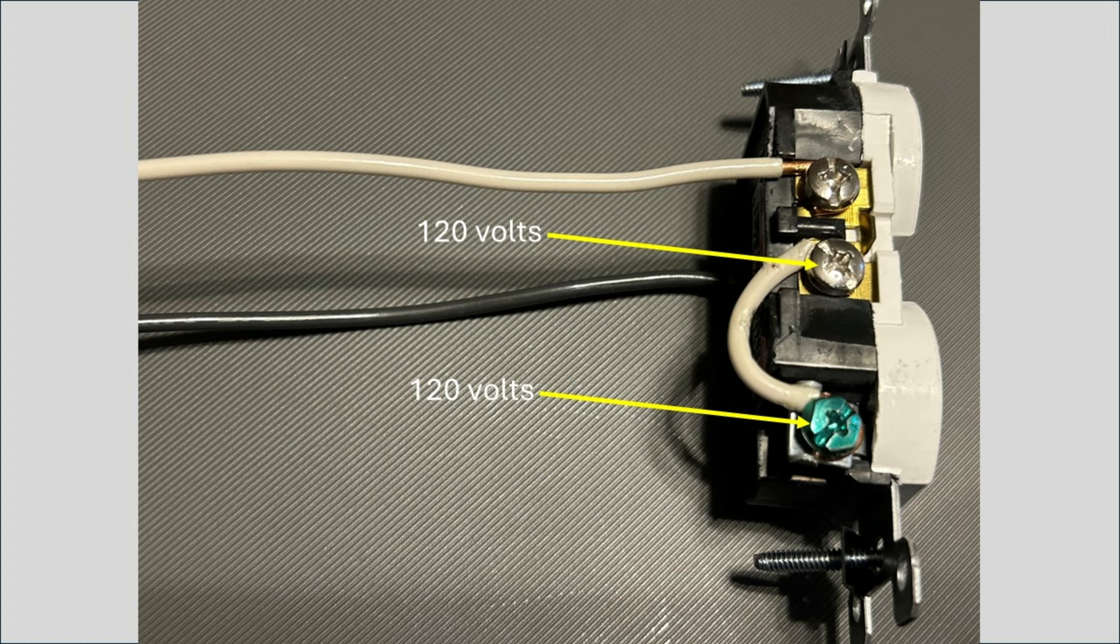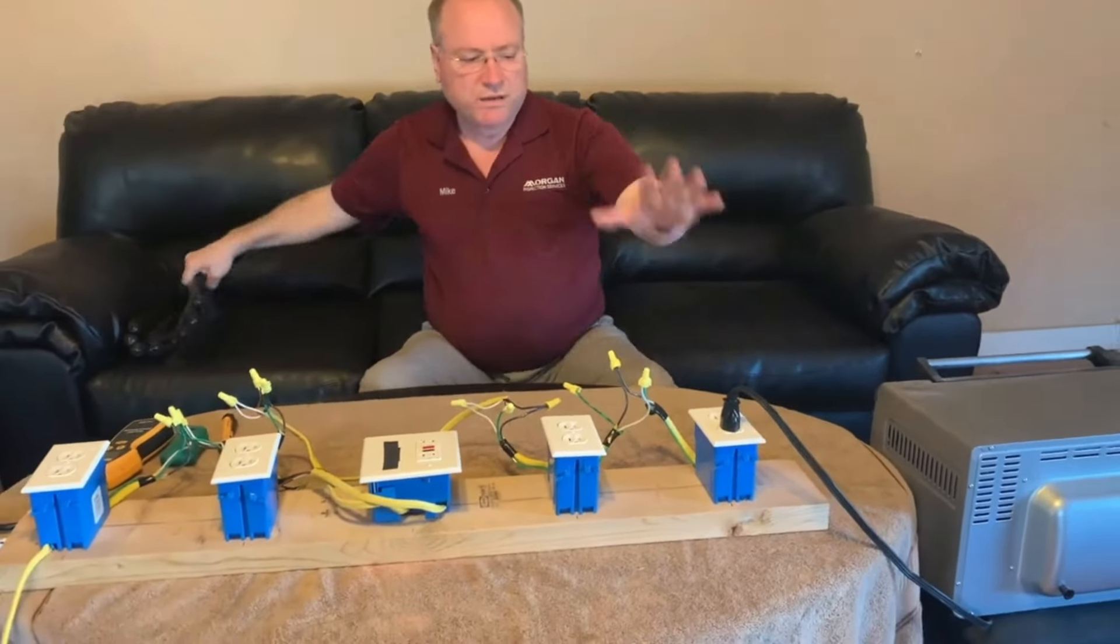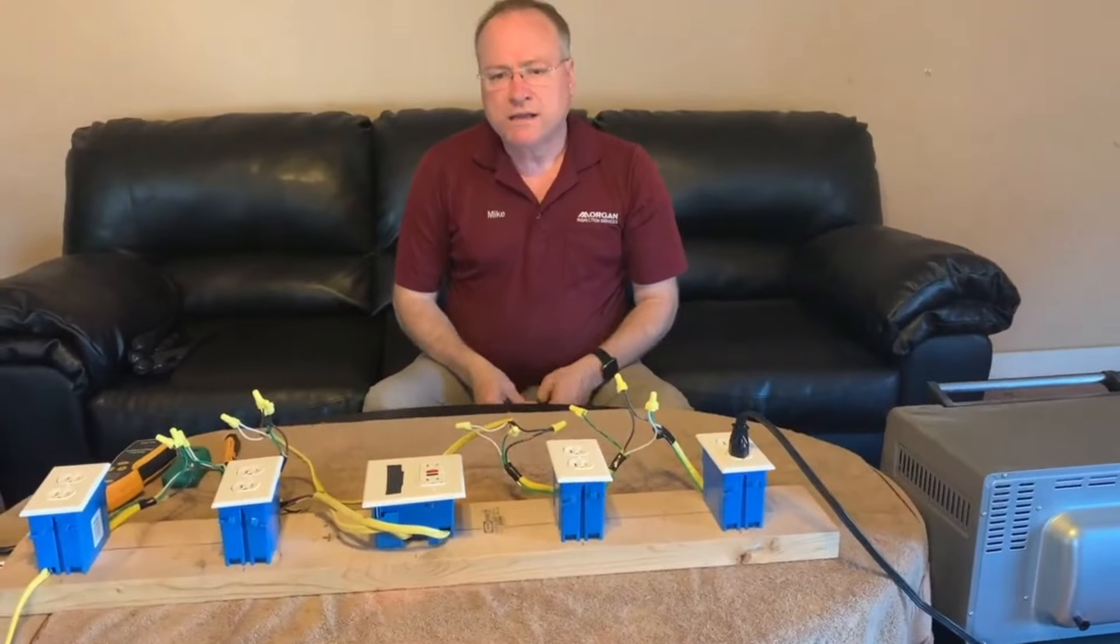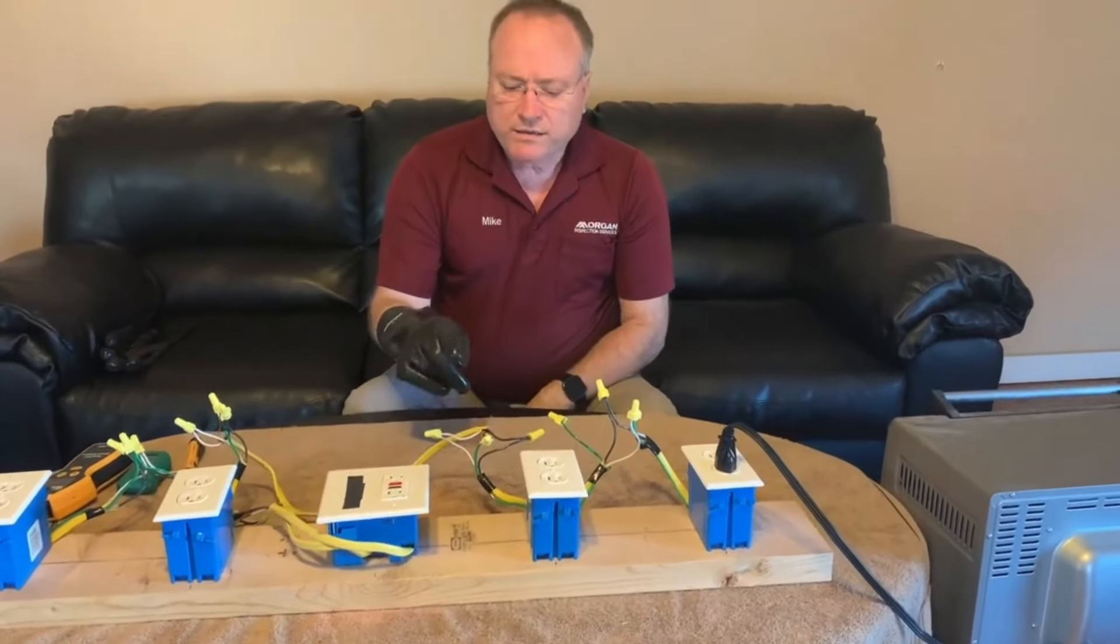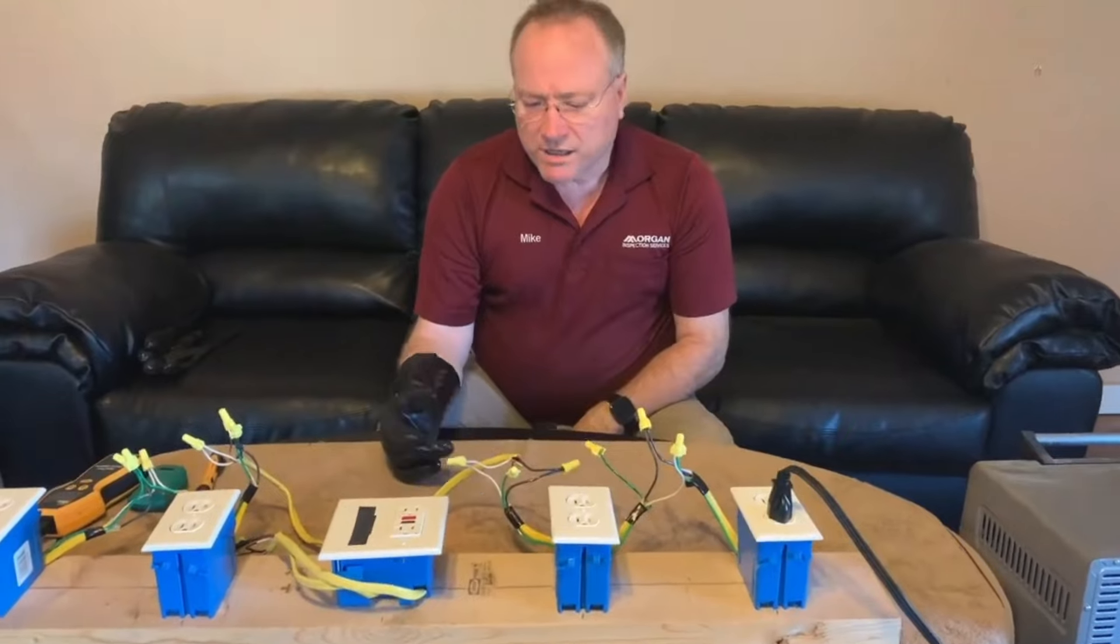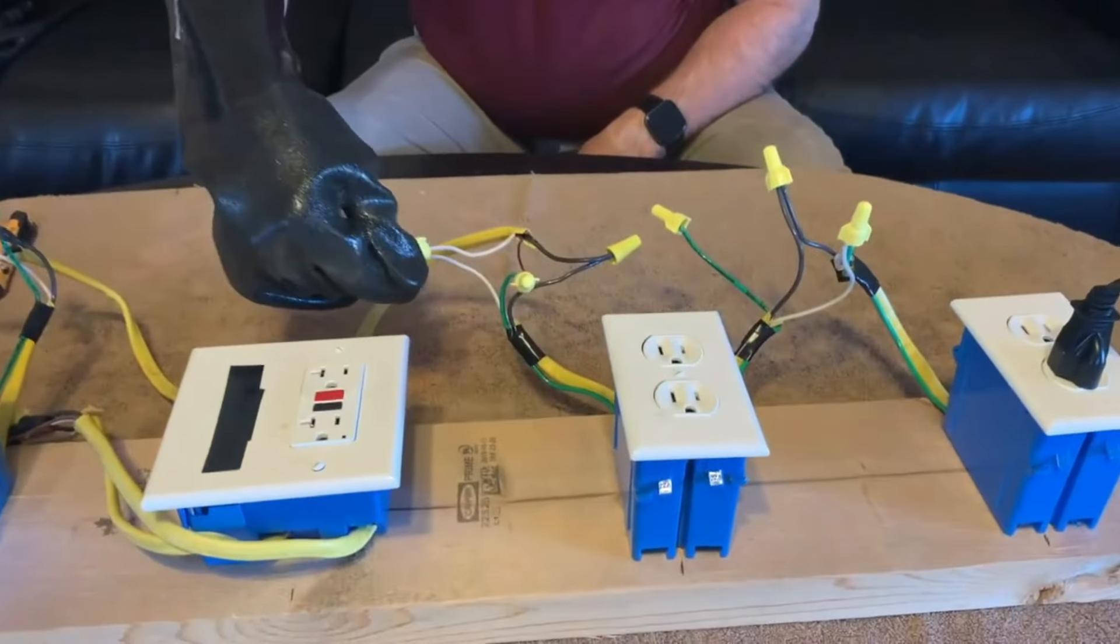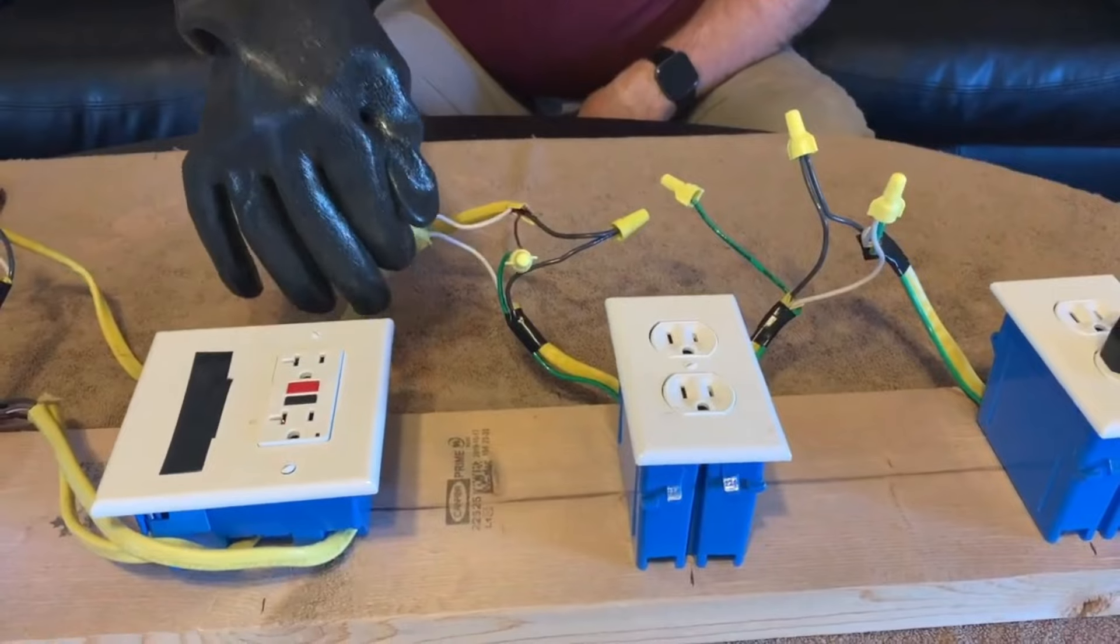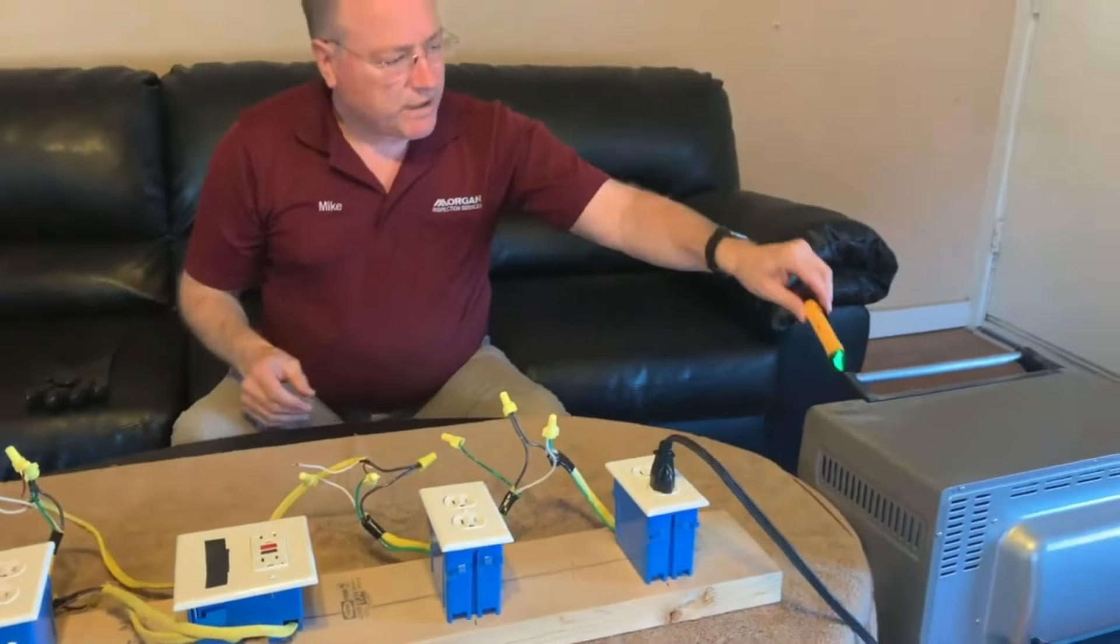And let's watch on my demo board what that does. Let's suppose that upstream of this outlet, maybe at another outlet, maybe in a junction box, maybe at the breaker panel, that a neutral wire comes disconnected. So I'm going to disconnect this neutral wire right here.